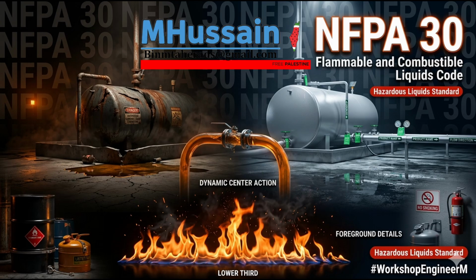It is. As an engineer, you must demand the precise safety data sheet. You must extract the exact closed-cup flashpoint and boiling point. The specific matrix classification, whether it's IA, IB, or IC, rigidly dictates every subsequent architectural, mechanical, and fire suppression decision. If you design the ventilation and sprinkler density assuming a Class II hazard, but the chemical is actually a Class IB, your building is legally non-compliant and inherently lethal the moment operations commence.